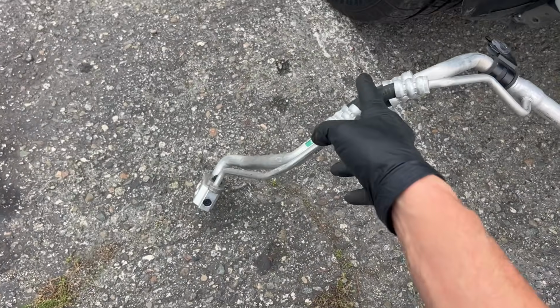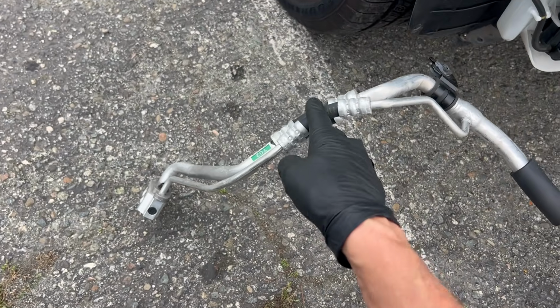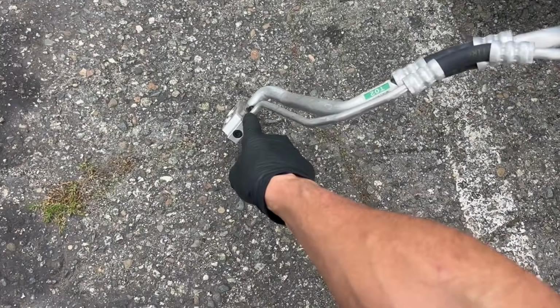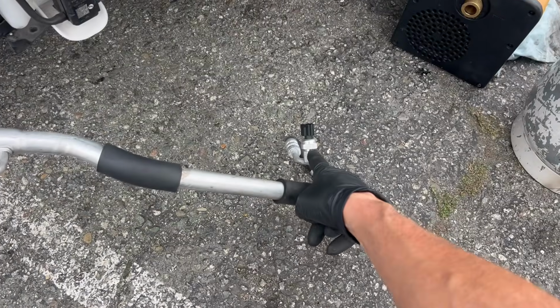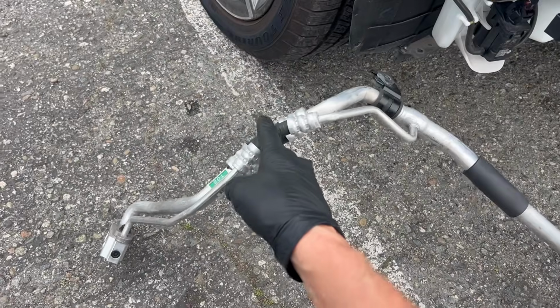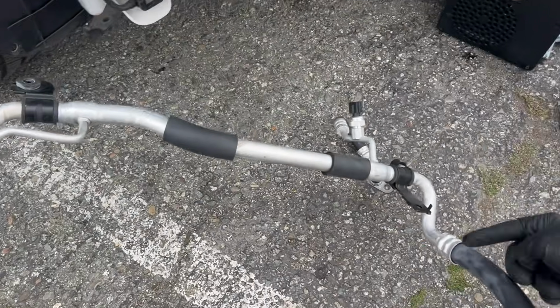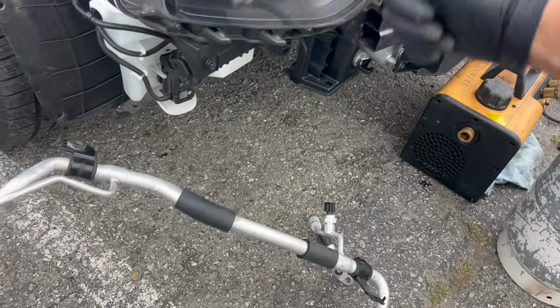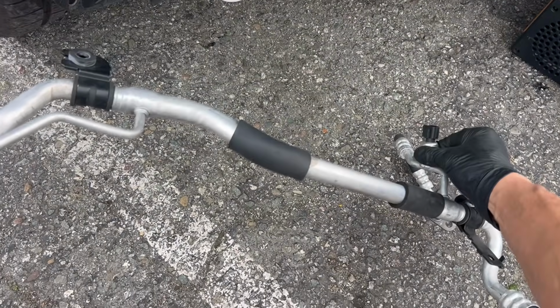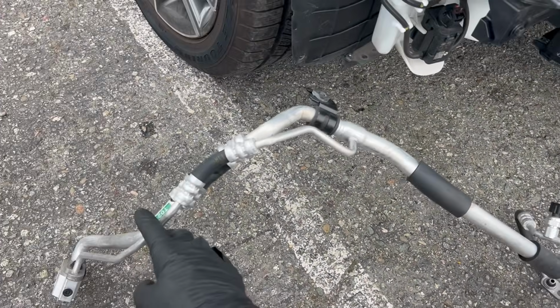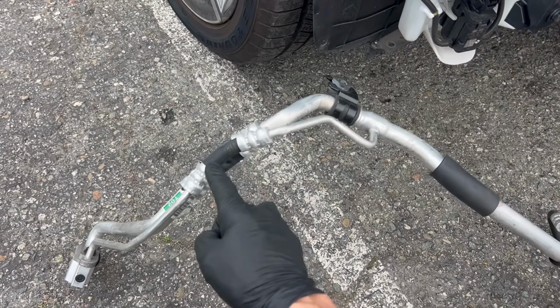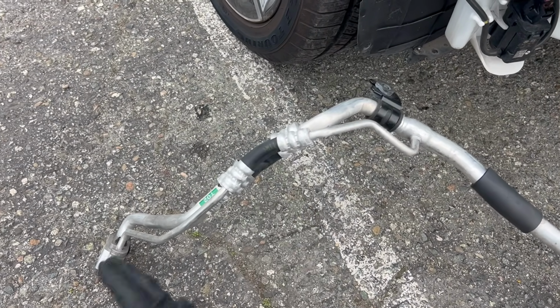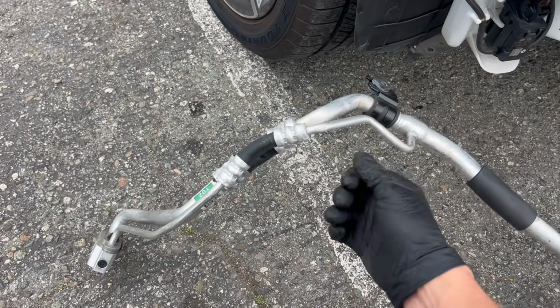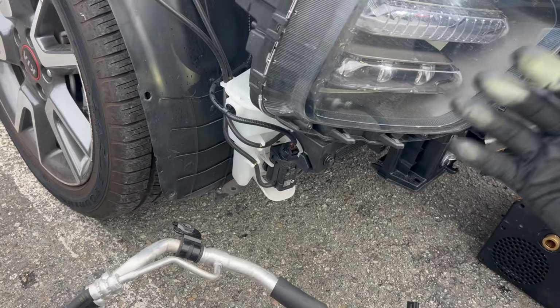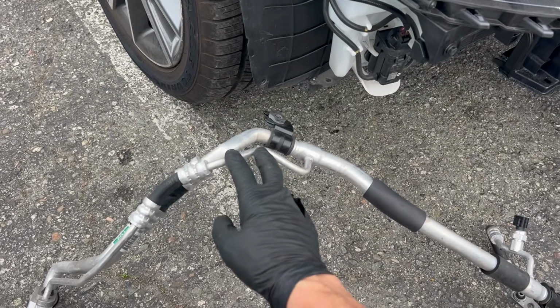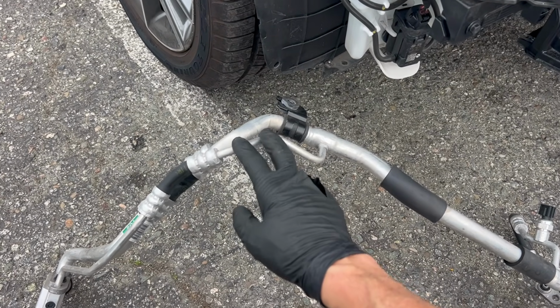You can literally add a crimp right here. Now, if I added a crimp right here, this is feeding to the expansion valve. You have a pressure transducer right here. So if I had a crimp right here, that means the pressure on this side going all the way back to the condenser would be unusually high, and it would read up here really high. So that means you put your temperature sensor here, you had an inner collapse at a section of hose right here. You might have, let's say right now, outside temperature is 70 degrees. So your liquid line right here might be 78 degrees or something like that.